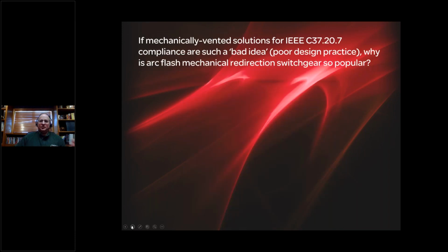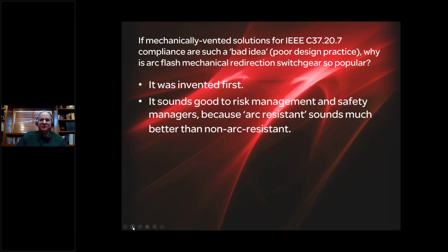So if mechanically vented solutions for C37.20.7 are, as I've stated in the previous slide, a bad idea, meaning specifically a poor design choice, why is arc flash mechanical redirection so popular out there? Because there's a lot of it out there being sold every day still. And one is, it was invented first. So in the early 2000s, when we began to quantify the risks via IEEE 1584 mathematics of arc flash events, the first solution was mechanical venting. It was simpler to implement, and it was there first, and it remains popular because of that.